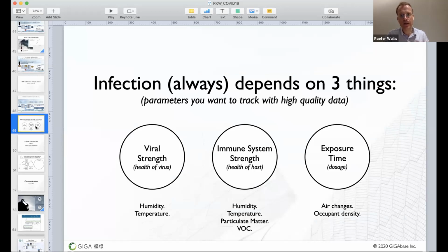So going back to these three pieces, what does that mean? It means, of course, a lot more tracking of humidity and temperature, not just as we normally do with thermostats within a space, but within the central mechanical system -- to look at viral strength, humidity and temperature, as well as particulate matter. And I guarantee you're going to see it in the headlines very soon: the impact of chemical off-gassing on viral transmission. So those parameters need to be tracked, and then exposure time tracked via air changes and occupant density.